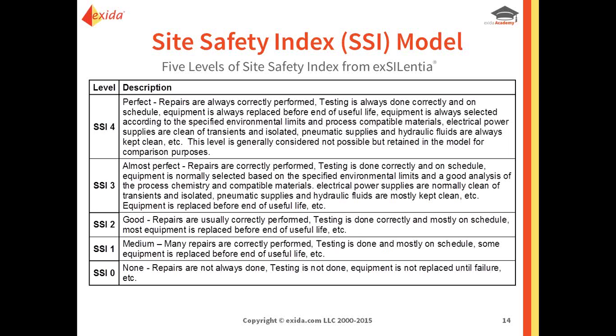Your repairs are usually correctly performed. Testing is done correctly. It's mostly on schedule. This might be a product where it's not critical to have everything perfect, and that's okay. But this is where I feel that, without these bases, failure rates were driven on SSI 2. So when we give a certificate, we're assuming that the end users have about an SSI 2, which is a great thing, because we have seen sites that are more down at the SSI 1 level, and there have been instances where there is an SSI 0. But we've never had a way to factor in these failure rates.